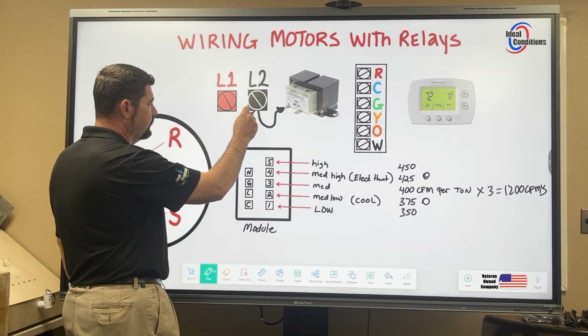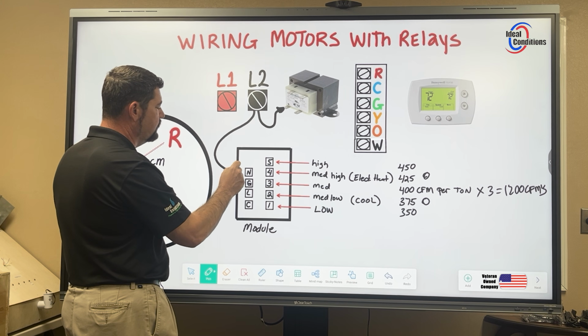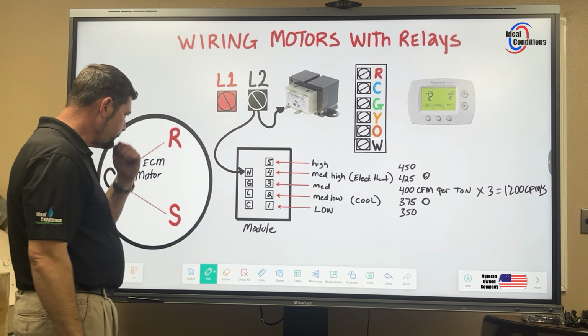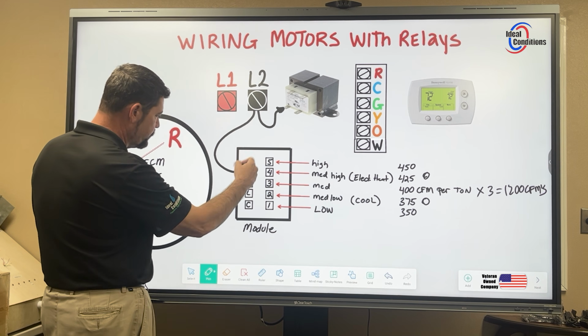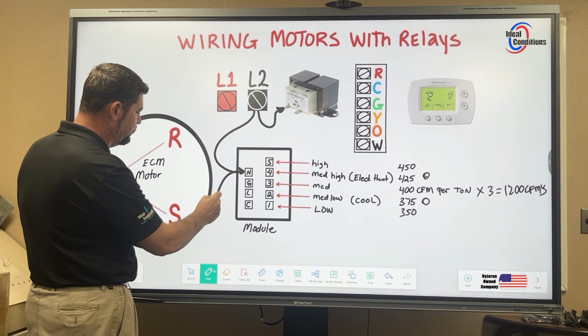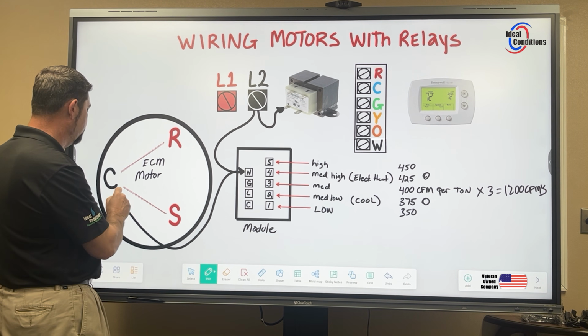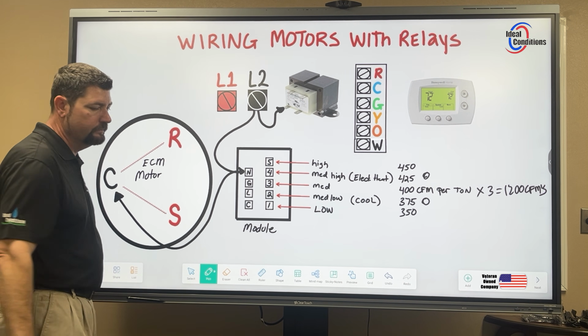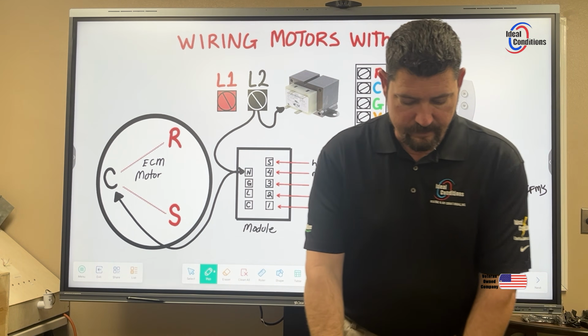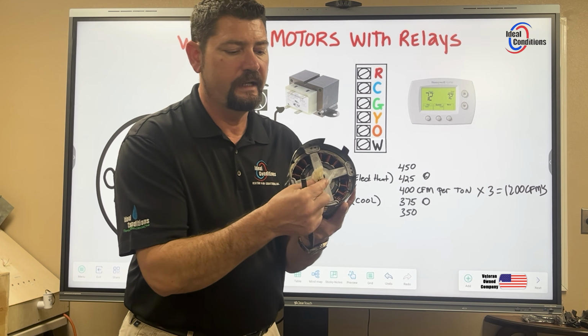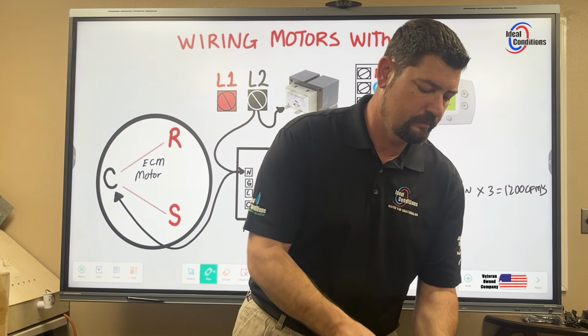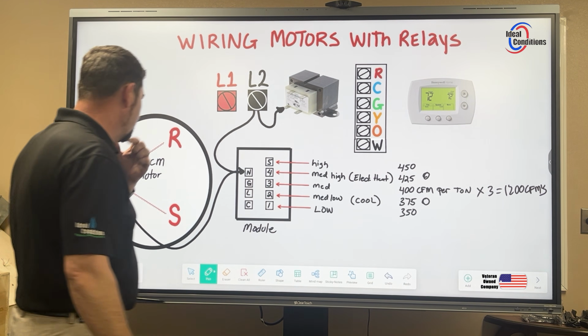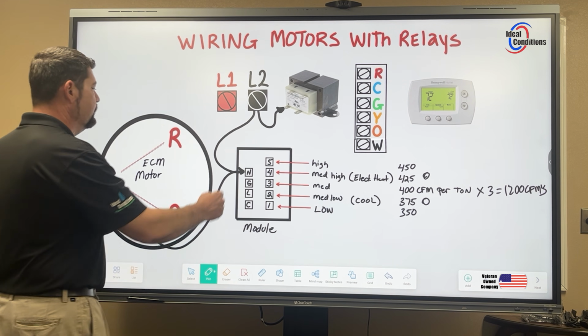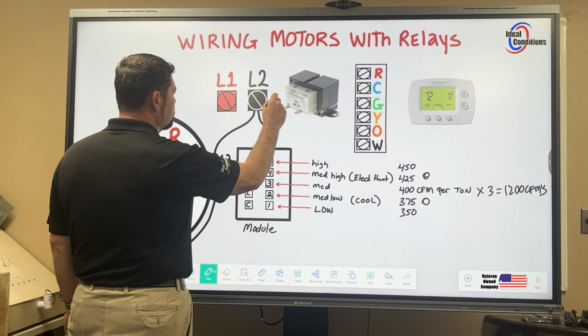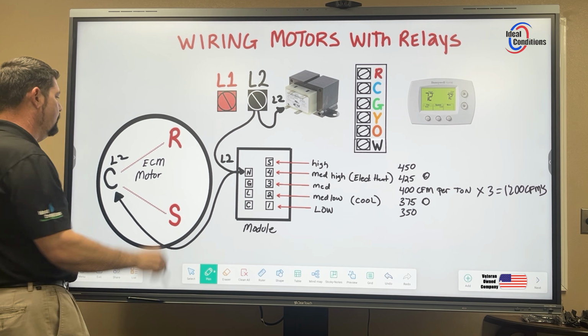I'm going to go ahead and take L2 as an input, and I'm going to wire to N. Now what's going to happen here is through the module, it's going to take N and wire it through that plug that we talked about to common. What I'm talking about is on the back side of this motor, this plug here, that's our 3 legs, our common, run, and start. All right, so we have L2 done. I'm going to go ahead and just label it L2, L2, and L2.